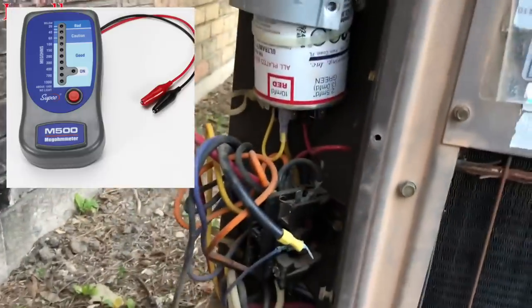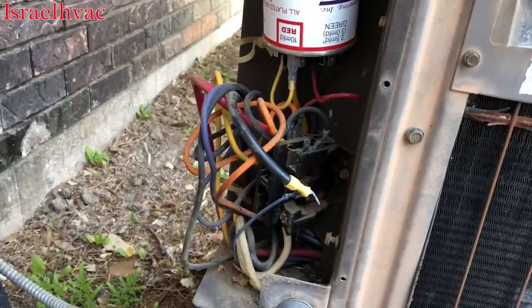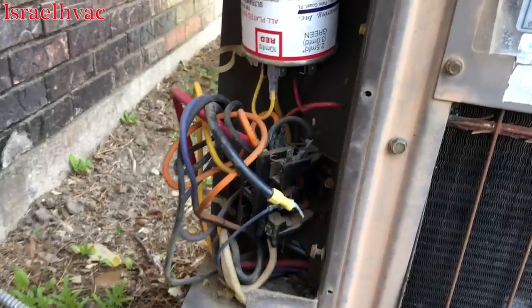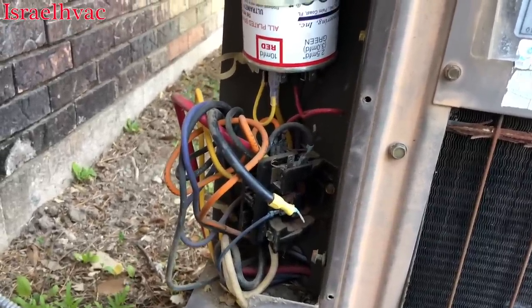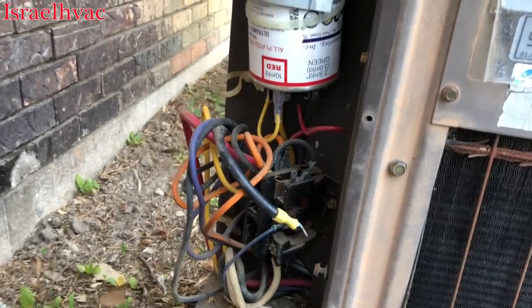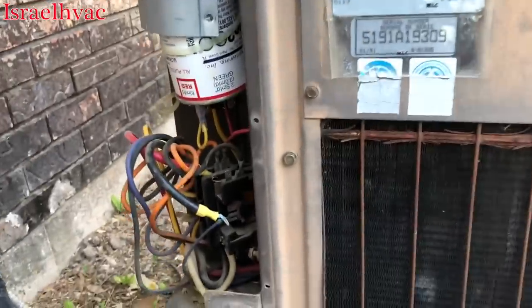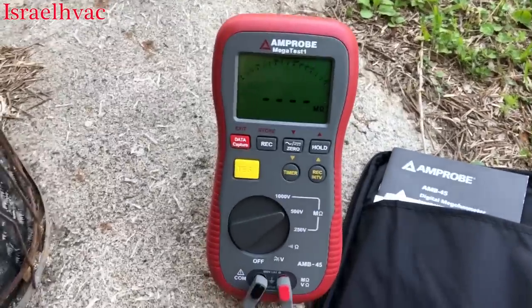A lot of guys like the Supco M500. I used to have it, but the problem is it's nothing but lights with numbers — you don't actually get a reading. If it's bad it shows 20 megohms with a red light, but 20 megohms doesn't necessarily mean failure. I've had compressors megohm out bad on the Supco and still run fine, so with this meter you get an actual reading.